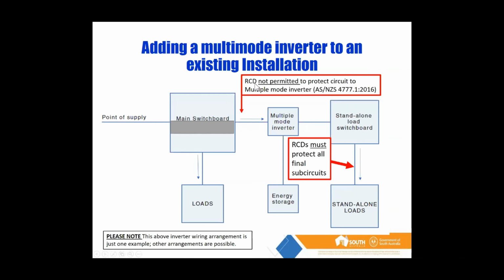First up, we really need to make certain that we're not putting an RCD on our multimode inverter. And there's a couple of reasons for that. The main reason is we need to maintain neutral continuity through to our standalone supply. The reason for that is if we take out our neutral, our MEN is in our main switchboard. So potentially we've lost our MEN, which is not good.